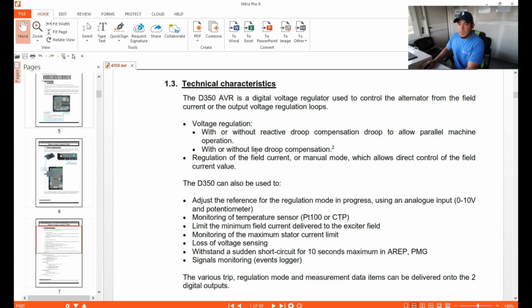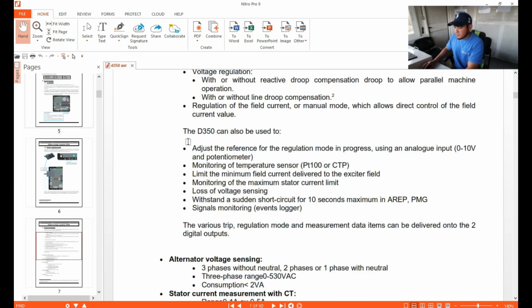In applications for synchronizing, this is a good AVR, very accurate and very perfect for synchronizing, and you can do everything you want with this AVR. It is designed so you can control or configure it through the software. The D350 can also be used to adjust the reference regulation using the analog input and a potentiometer. It is stated here that the analog input can be used by the synchronizing, which you can adjust automatically through the module. This one is 0 to 10 volts, and you can also use both at the same time.